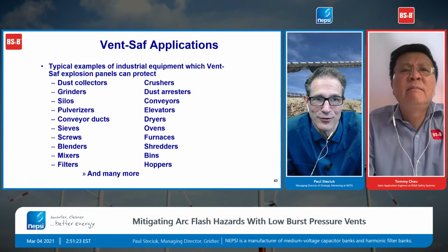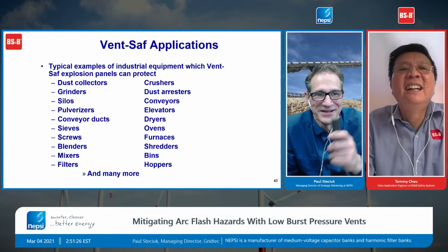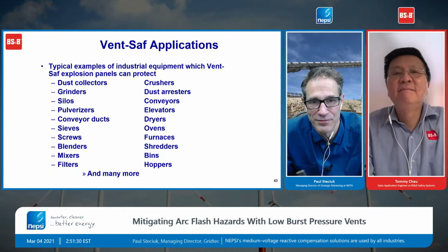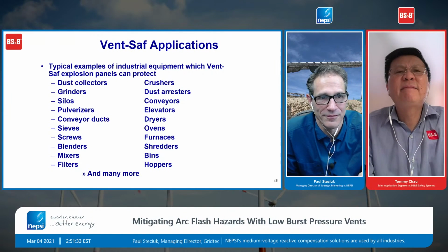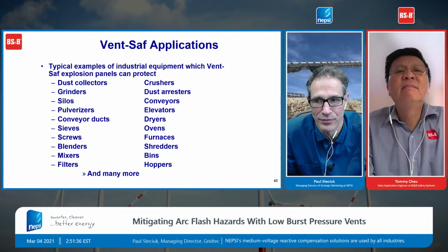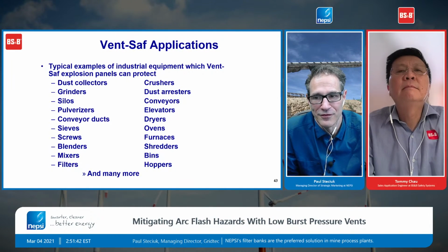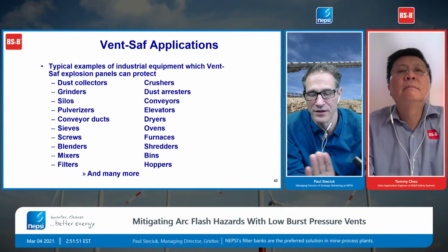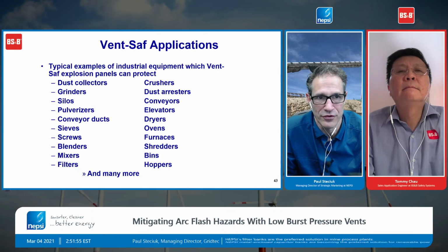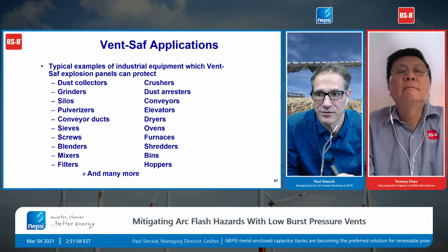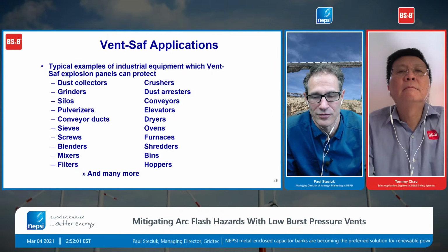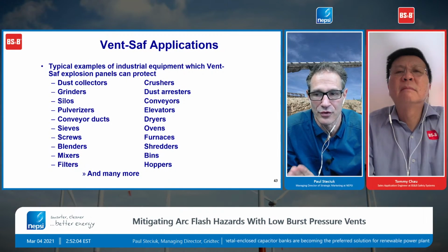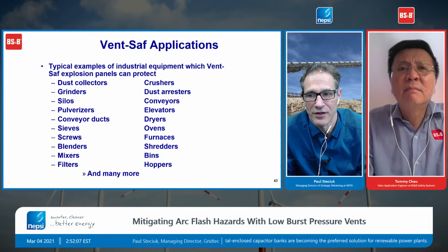You don't have capacitor banks or harmonic filters listed there, so you've got to add them to the list. And for those out there specifying custom electrical equipment, think about using these low burst vents. It's a pretty inexpensive way to provide a degree of arc flash protection for the people working on the equipment. Not that expensive, not difficult to do. You figure out an area, a safe zone, put the vents on that side of the equipment, and you've got some protection for your workers. And that's really the purpose of this presentation today: think about using this on your metal enclosed cap banks and filter banks and other electrical equipment that's custom in nature, where arc flash testing is cost prohibitive.